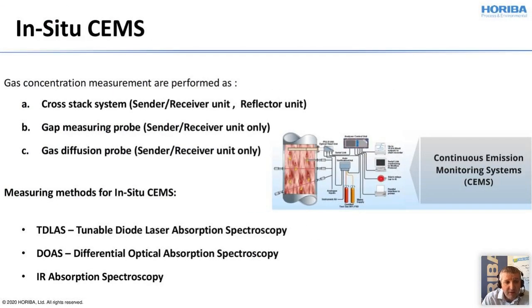Next topic I have is about the gas concentrations measured with in-situ CEMS. Gas concentrations are measured as cross-stack systems, where you have the sender and receiver on one side and the reflector unit on the other. You have a gap measuring probe, which just enters on one side, or a gas diffusion probe, where you also have the sender and receiver unit only on one side. The methods for in-situ CEMS are tunable diode laser absorption spectroscopy, TDLAS, or DOAS, differential optical absorption spectroscopy, or finally also infrared absorption spectroscopy.